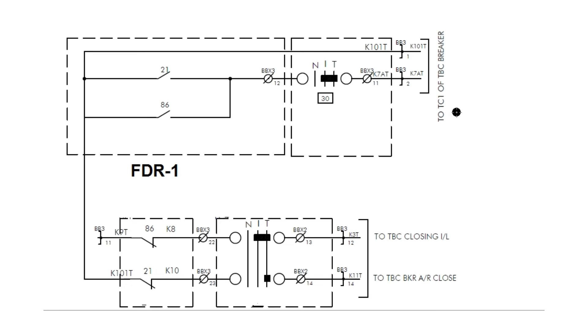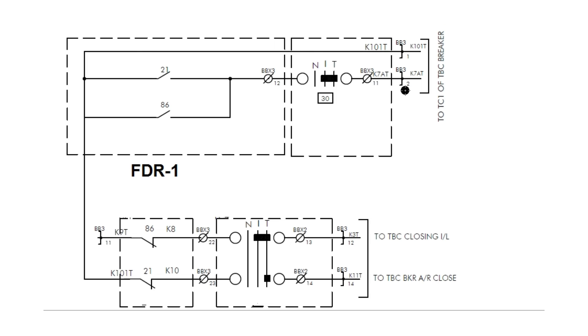The TBC tripping circuit shows how the trip is transferred from the feeder 1 panel to the TBC breaker. K101T — that is the positive DC of TBC 1 — is coming from the TBC panel. 21 is the main relay, that is a distance relay of feeder 1 panel. If a fault occurs in feeder 1, the distance relay 21 will detect this fault and send the trip signal to the master trip relay of its own panel. Via the 21 relay contact and 86 relay contact, the positive DC will flow and it will transfer to the TBC panel via the NIT switch contact in inter and transfer position. If the NIT switch is in either inter or transfer position, this trip will be transferred to the TBC breaker and the transfer bus breaker will be tripped. This is the TC1 for the TBC breaker.